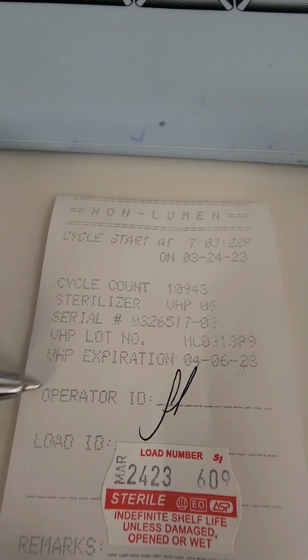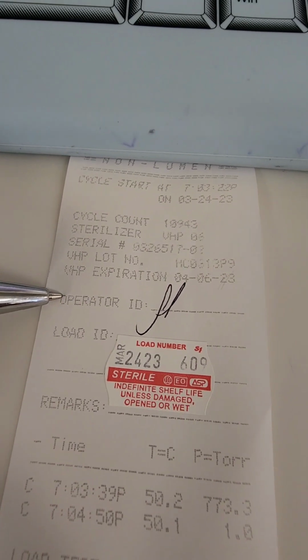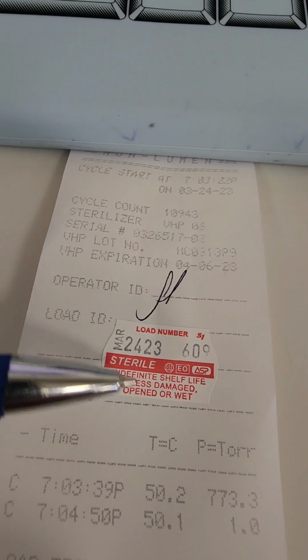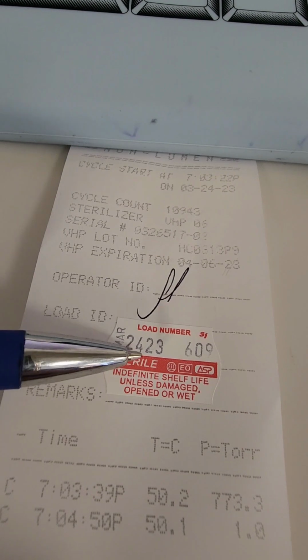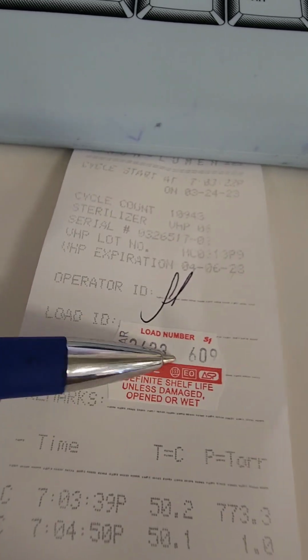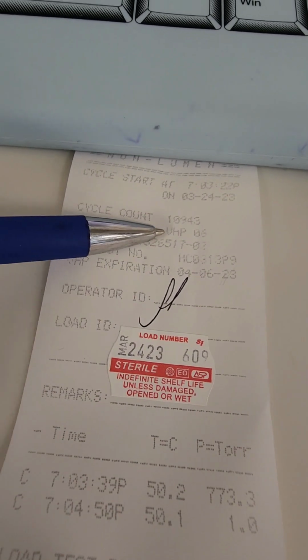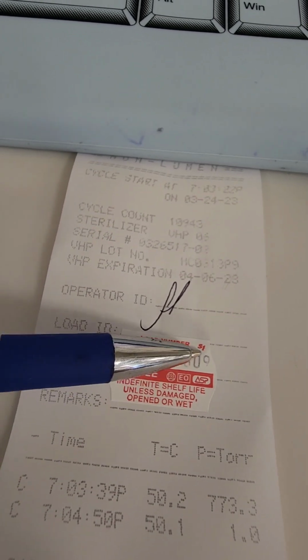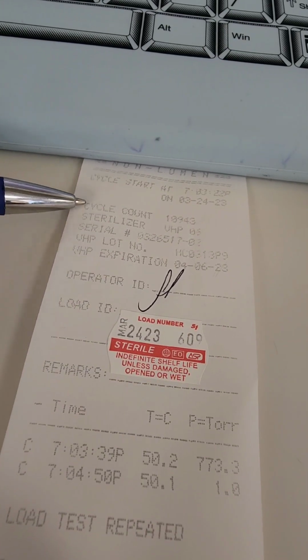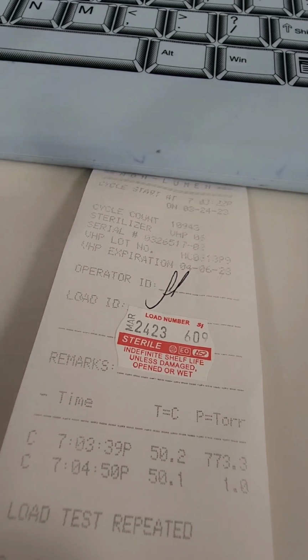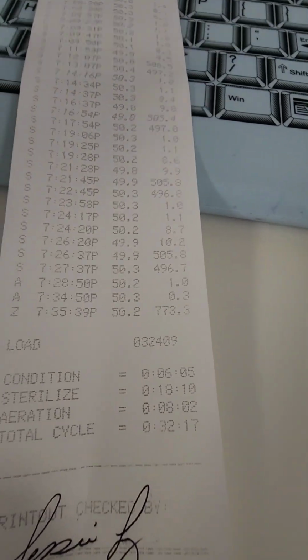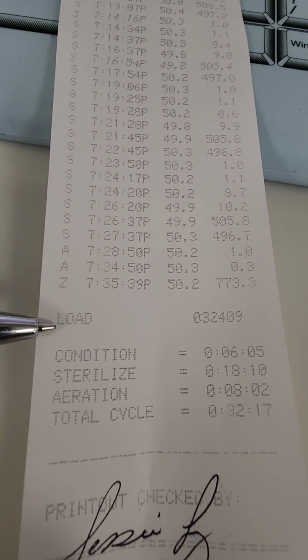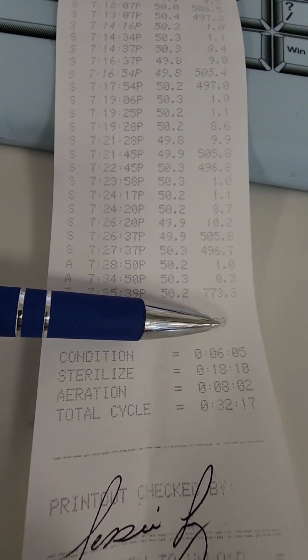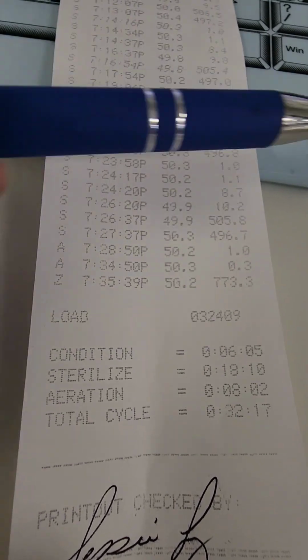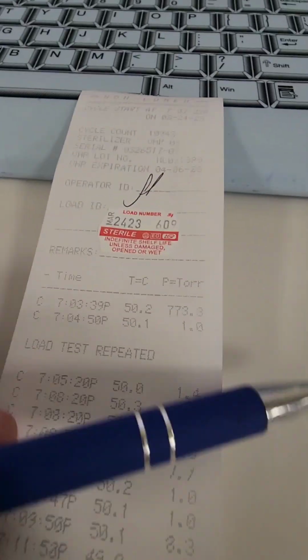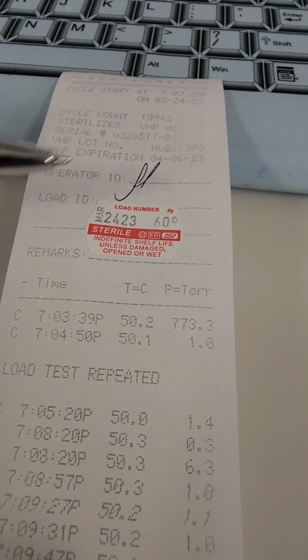Okay. The next line is the operator who started the machine, and then the lot number that you place on each device. So it tells you when it was done, what sterilizer, and what load. So where do I find that load? I showed you the sterilizer name, but the load number should match the printout. That load count is not the load cycle. It's the load right there. See that load? Now, it's a really long number, but the last number is the one that correlates with the cycle. So this is sterilizer number 6, load number 9.